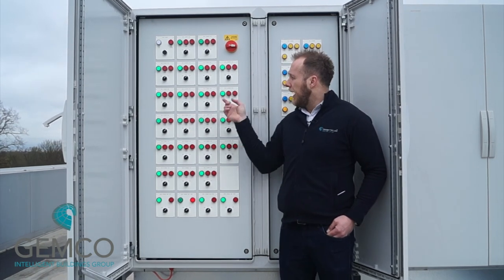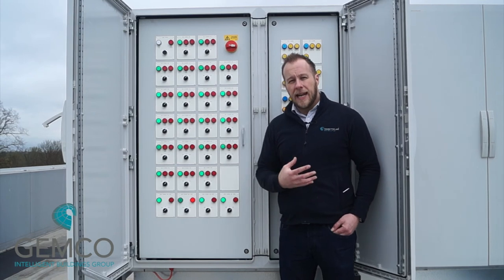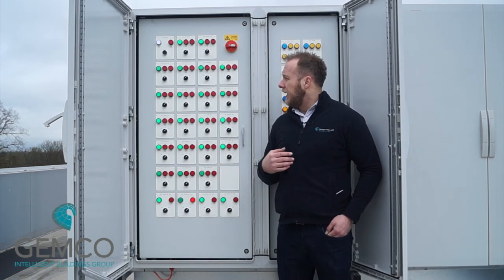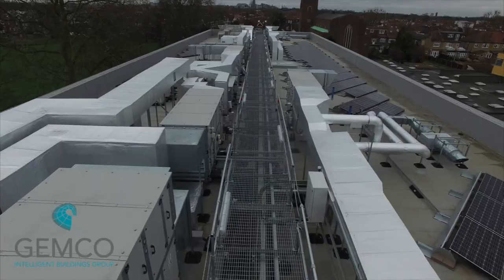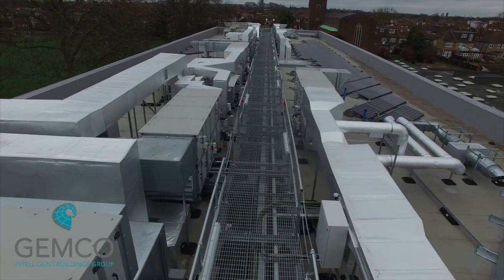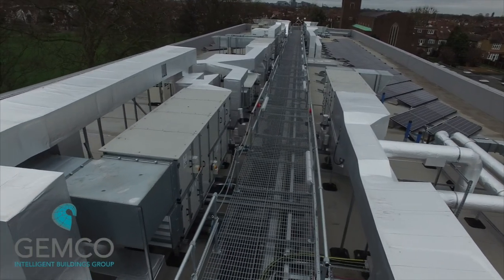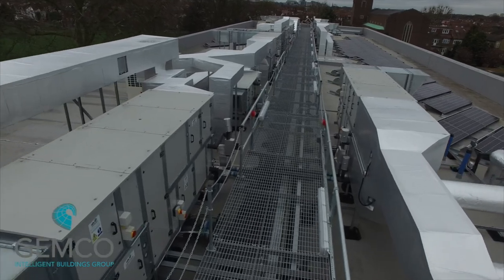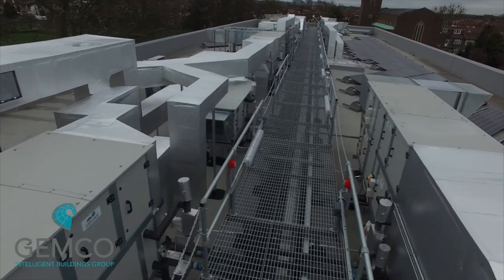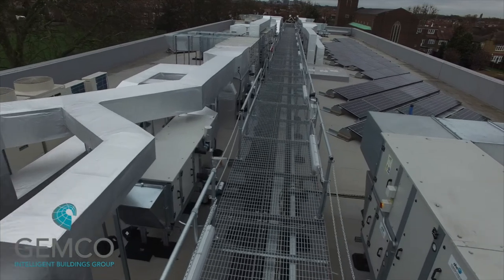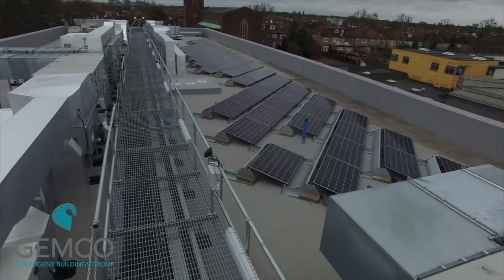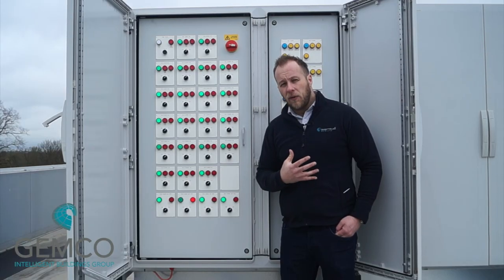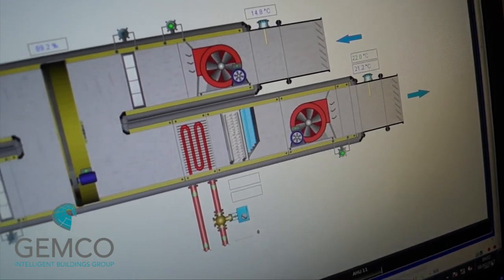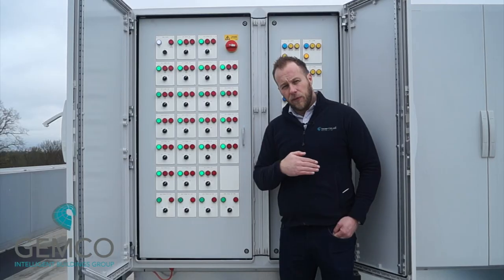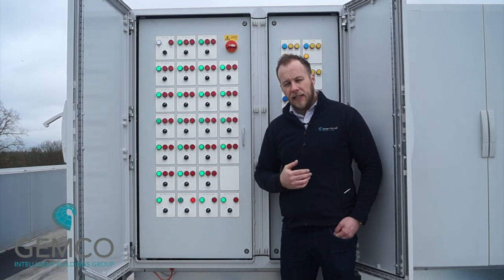Okay, now there's a few lamps. The green lamps are all enabled or running, and the red lights are fault. The middle red light on each of these labels is a flow failed lamp. When the fan is enabled and the damper starts to open, until the fan's running and that differential pressure switch is made, that light will be lit to let you know the flow has failed at the moment.